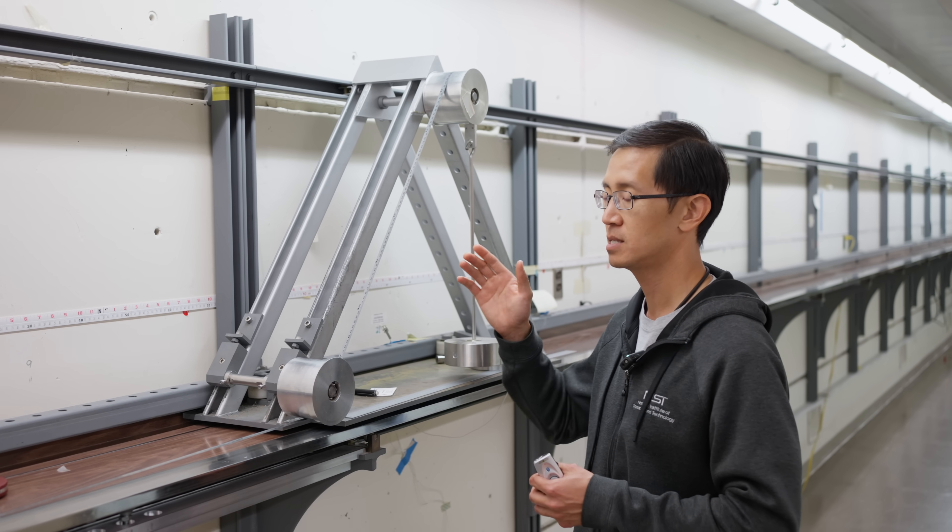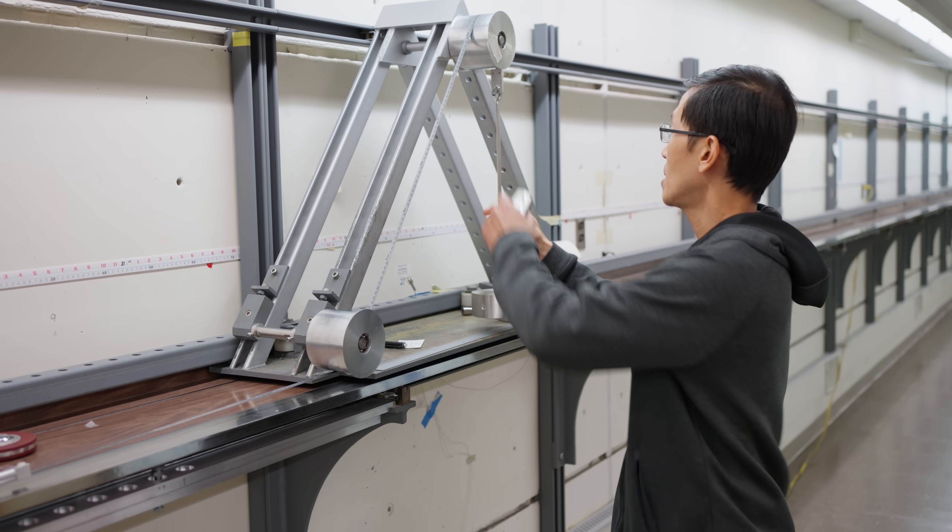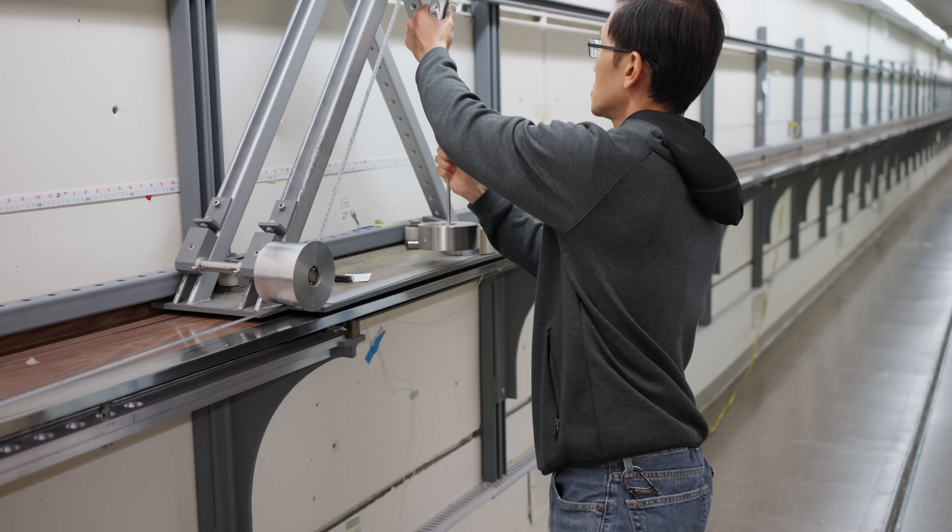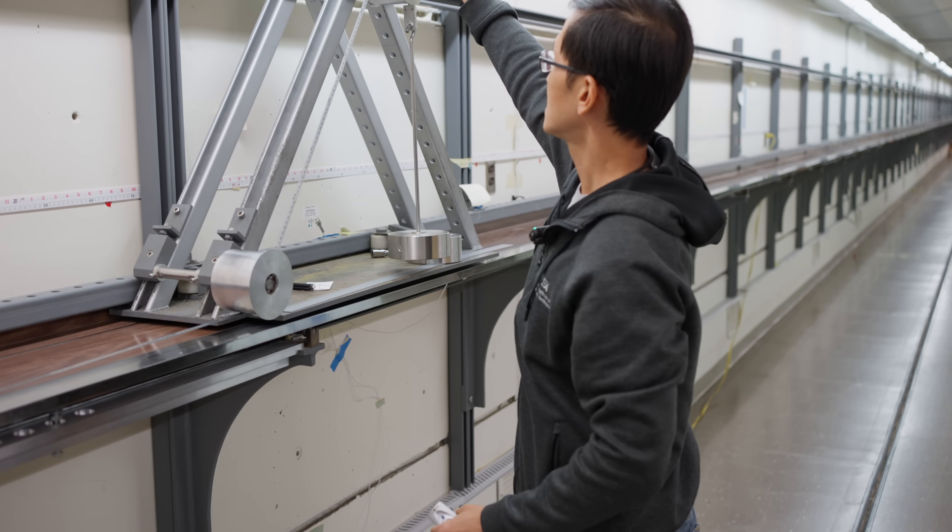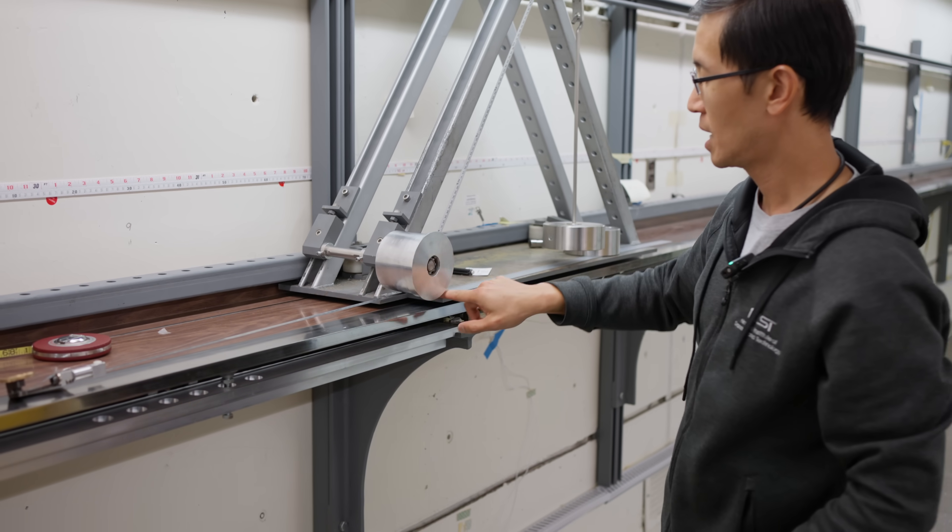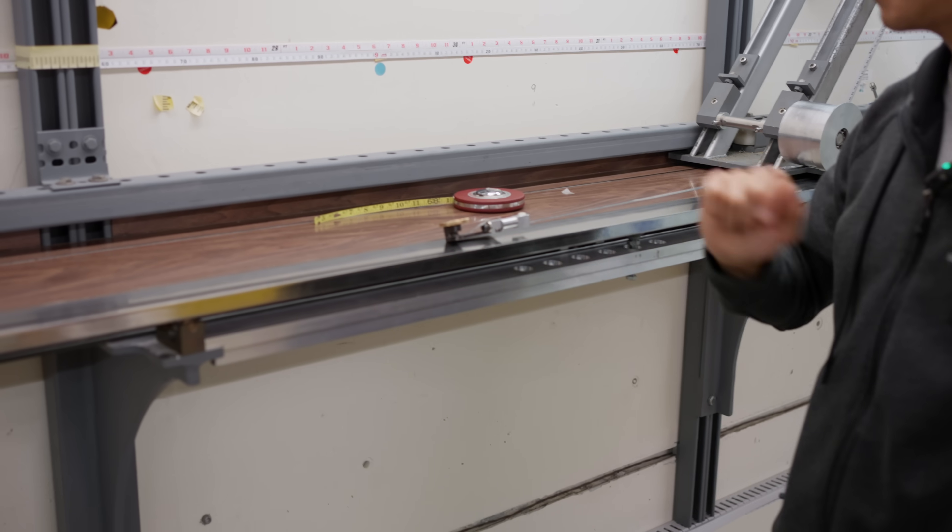So, right now, this is a 7-meter-long tape. I have 5 kilograms applied to it. So, it's simple, deadweight loading. So, it hooks onto here. There is a metal tape, which goes along this pulley and runs along here and clamps onto the tape being tested.